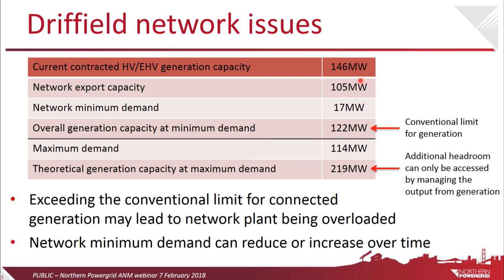So right at the top of this slide, we can see that we've got about 146 megawatts of contracted generation that's either already connected or accepted. The export capacity for generation in this bit of the network is 105 megawatts. That's the next point in the table down, with a minimum summer demand there of 17 megawatts. And if you add the two together, it gives us an overall generation capacity at minimum demand of about 122 megawatts.